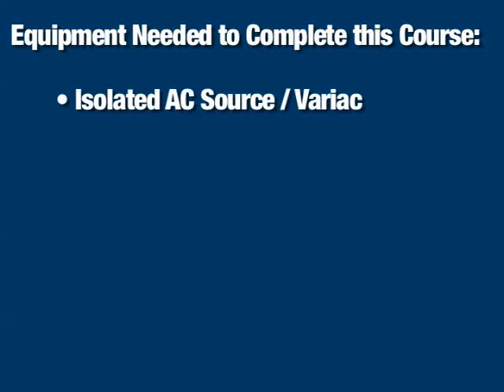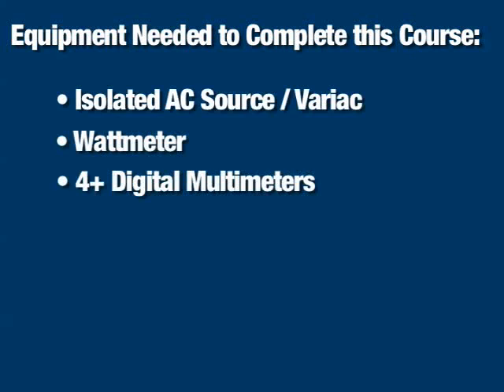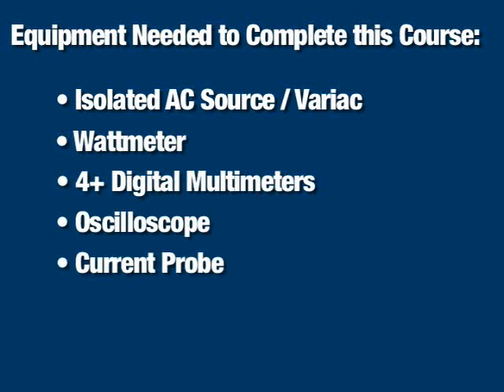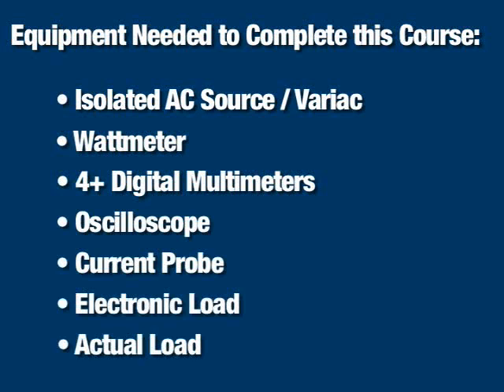To complete this testing, you'll need the following equipment: an isolated AC source or variac, a wattmeter, at least 4 digital multimeters, with 2 of the 4 having a high-resolution current range, an oscilloscope with a high-voltage probe, a current probe, an electronic load, and your actual load.